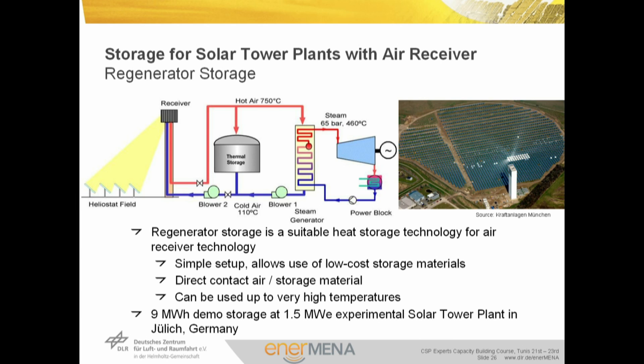Solid storage materials are also preferred for solar tower plants using air as a heat transfer medium. The regenerator storage is the suitable heat storage technology here. The setup is simple and allows low-cost storage materials. Direct contact between air and storage material is possible, decreasing the temperature difference between working fluid and storage material, and a very high upper temperature limit is available. A first demonstration unit with a capacity of 9 MWh thermal has been erected at a solar tower plant in Jülich, operating with a 1.5 MW electric power cycle.